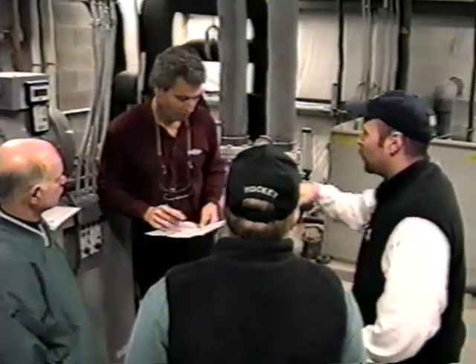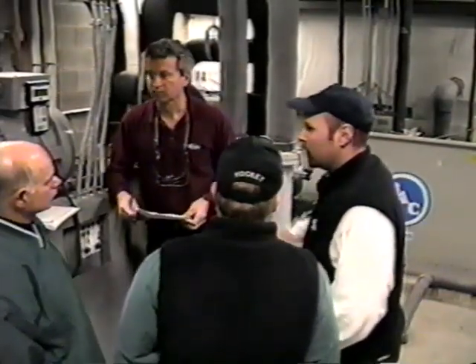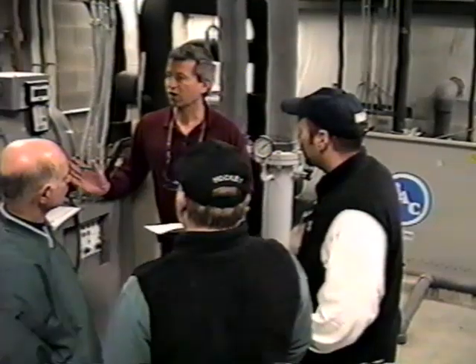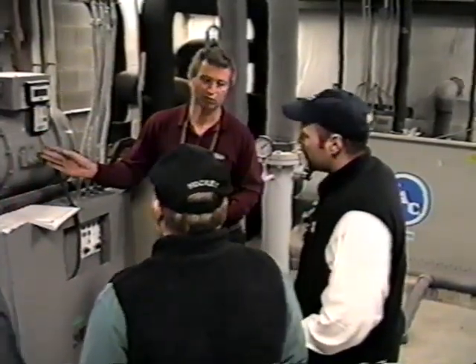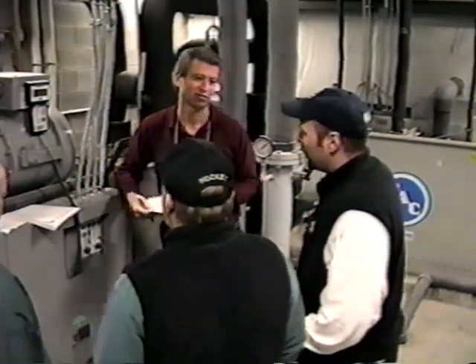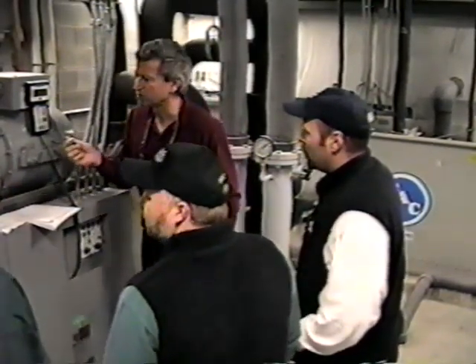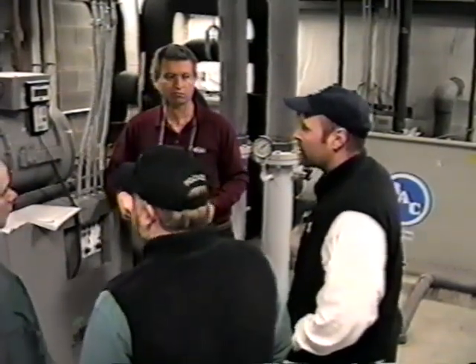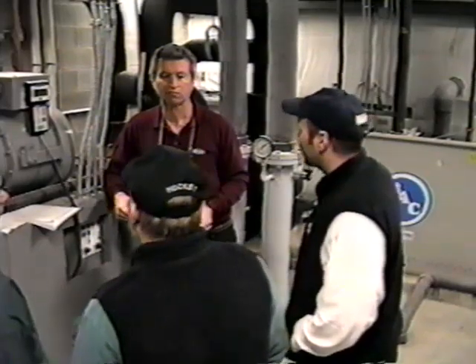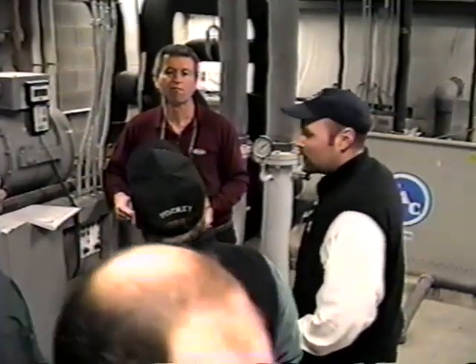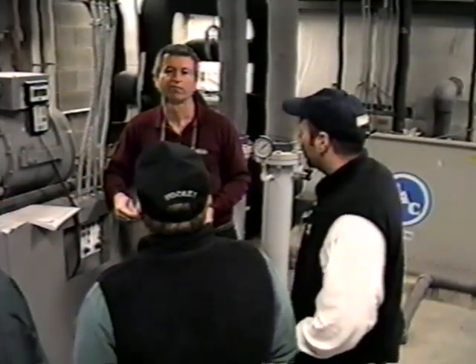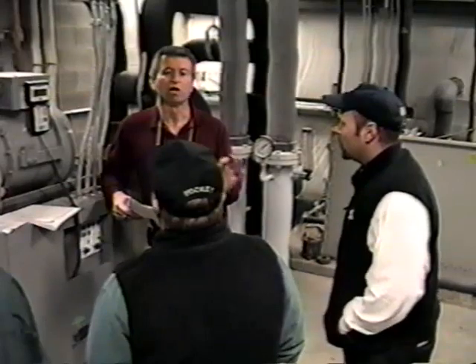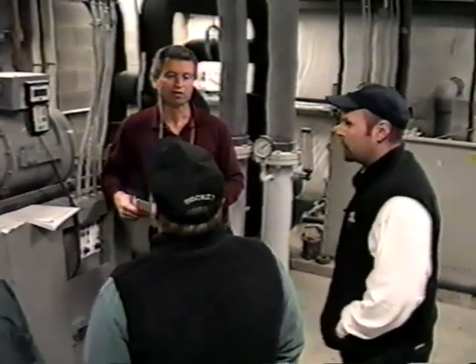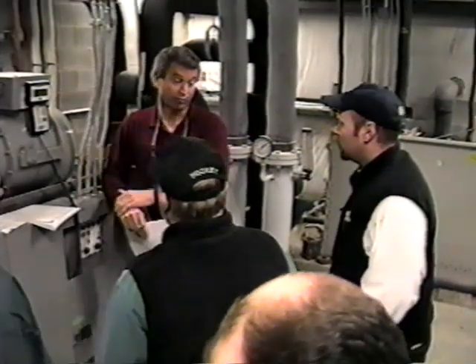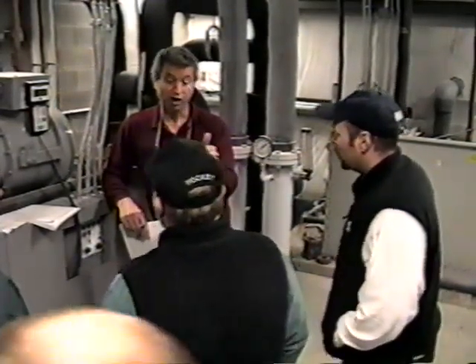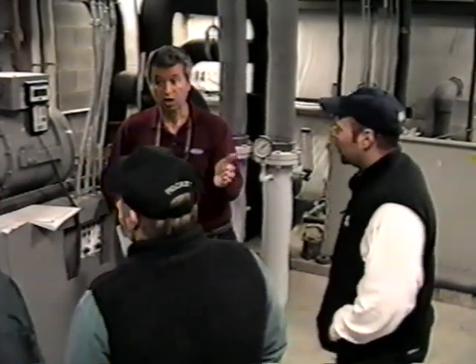Okay, so this one, the one we're running at 55%, it says, of the total capacity of the machine, one does 55% versus 45% for the other, so they're pretty close. And one always runs first, like compressor P1 will always start the load. So the run hours roughly should be 55, 45? No. It just looks at those numbers as far as hours and starts go. Okay, so when we turn this on again, B should start first because it's got the lowest number of hours and starts. Oh, okay. Again, it's the sum of those.